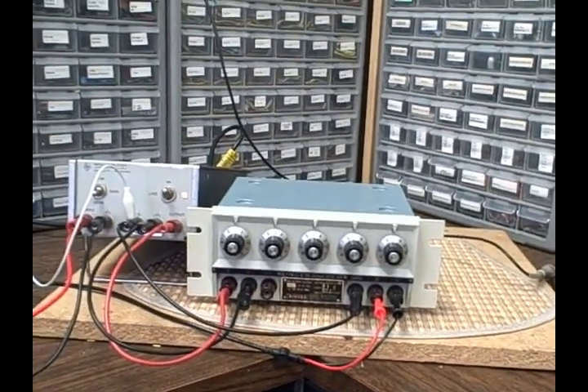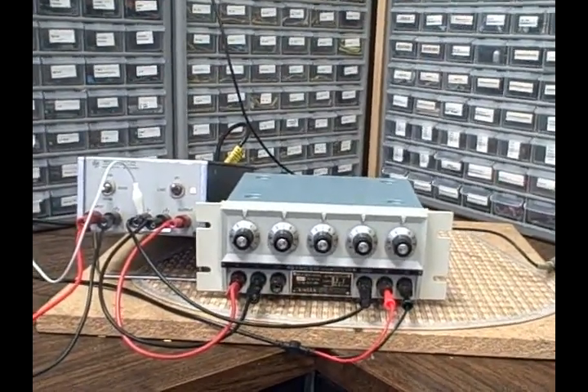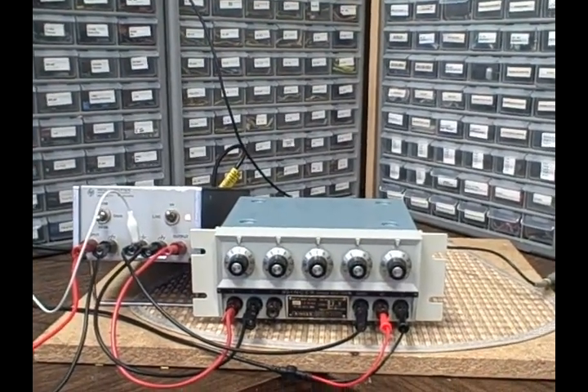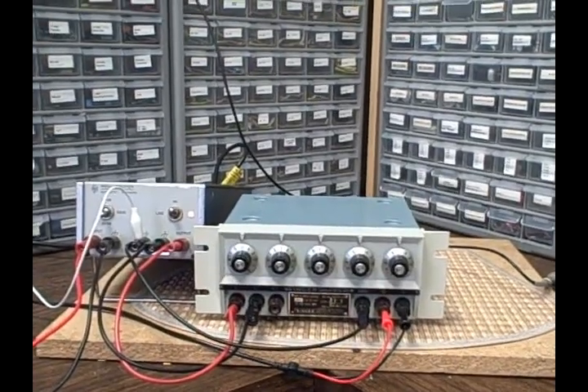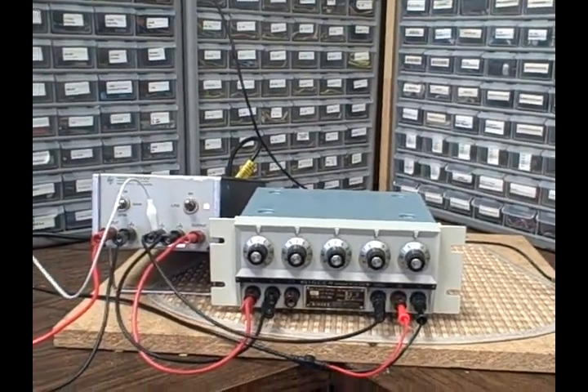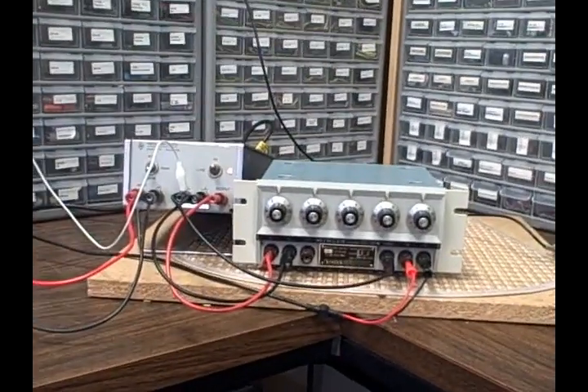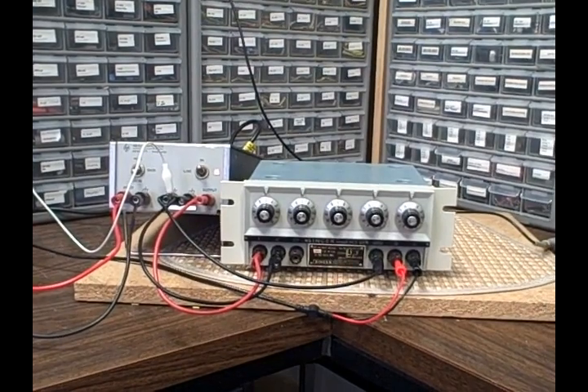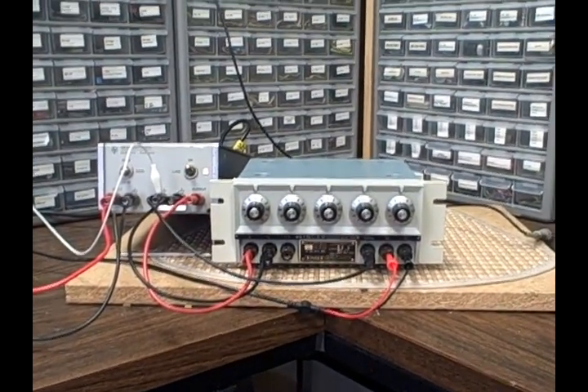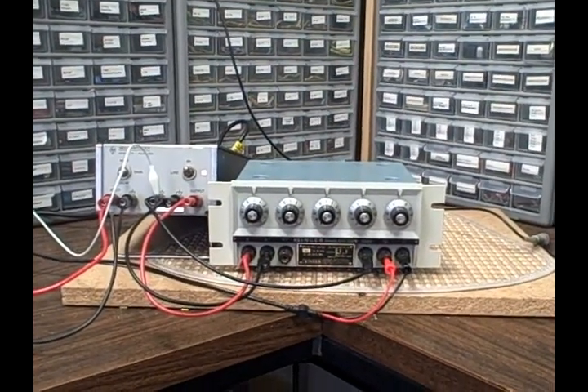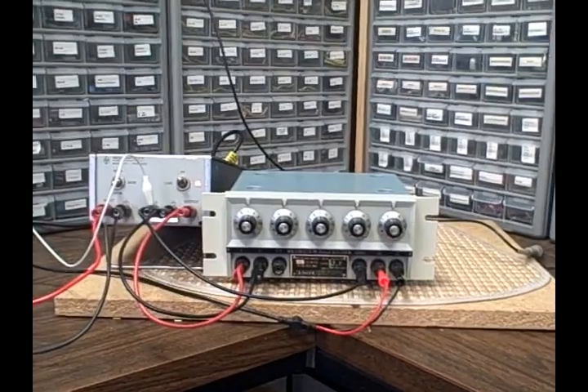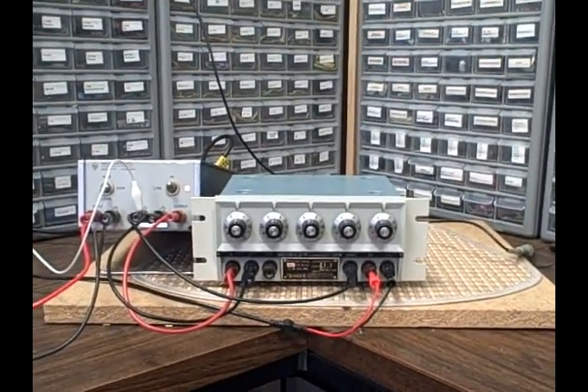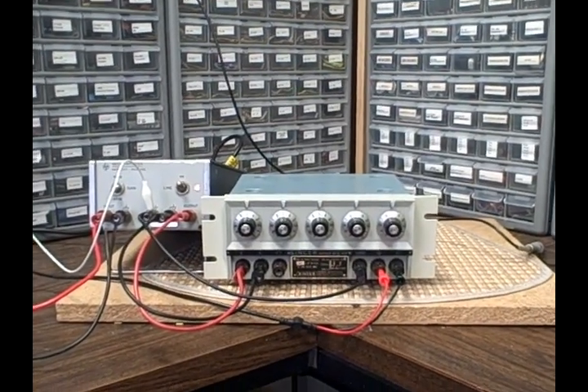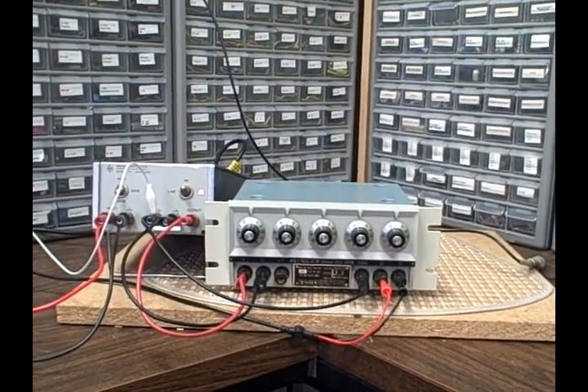So there you go. There's a little introduction to a ratio transformer. What are they used for? They're used for calibrating meters, providing AC calibration voltages for use in oscilloscopes or anything. You could use it on the input of an amplifier that you want to test. You provide a very known input down to a thousandth of a volt, and then you can calculate your gain, for instance, to within, say, a gain of 1,000, and still maintain a really high percentage of accuracy. Anywhere that you need a calibrated AC voltage, so you think it up. Bridge circuits would be another one.